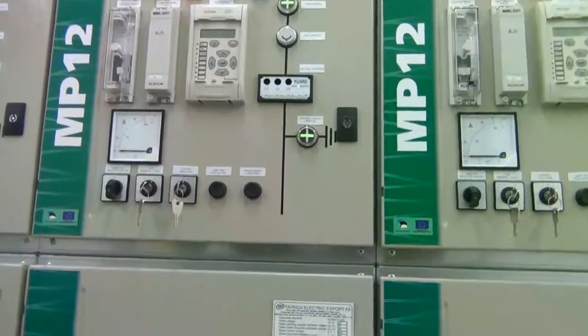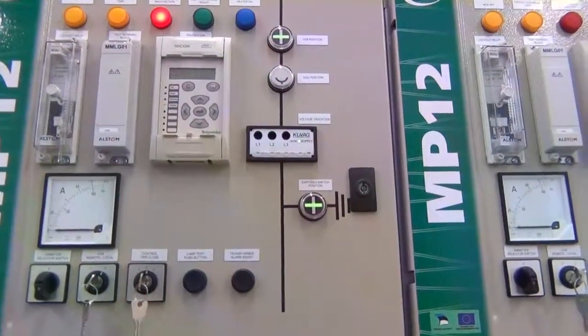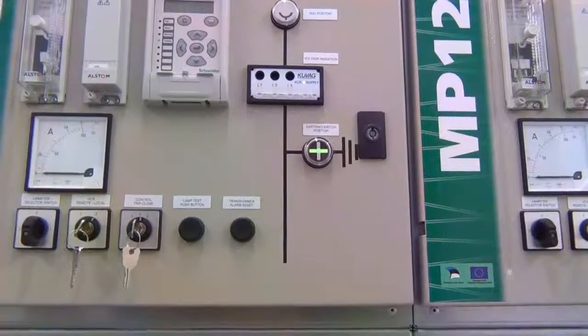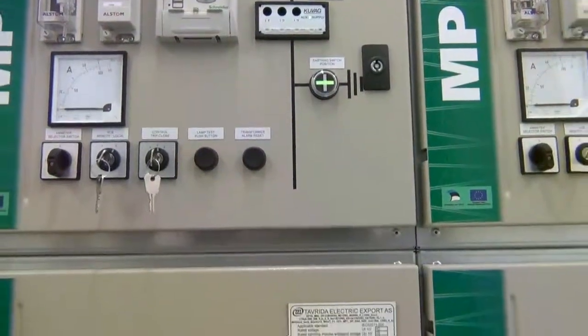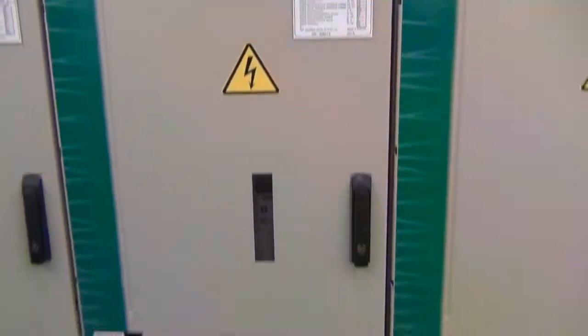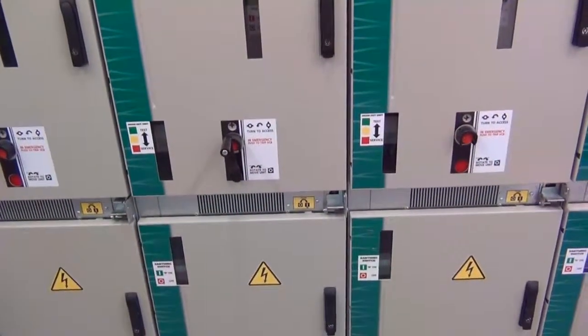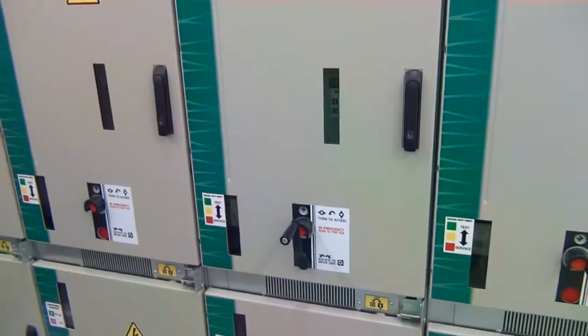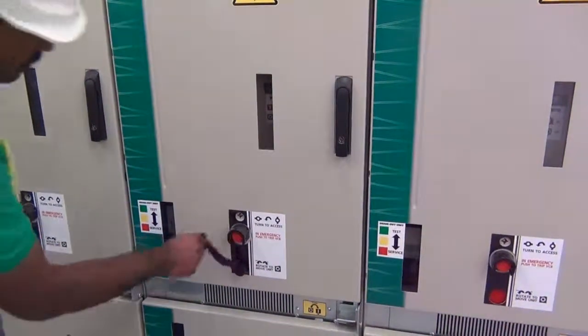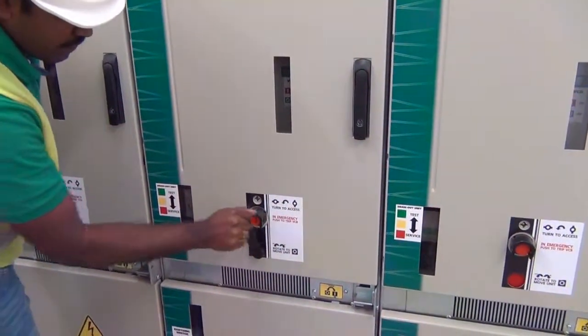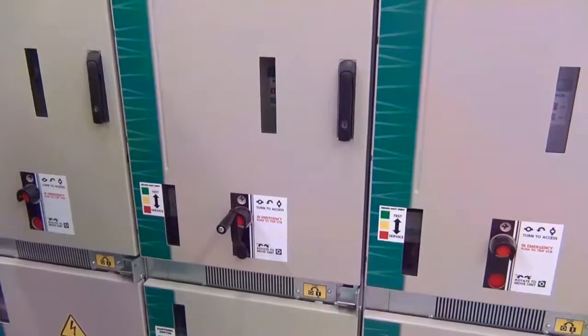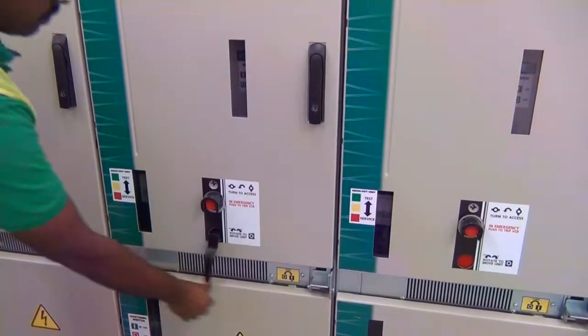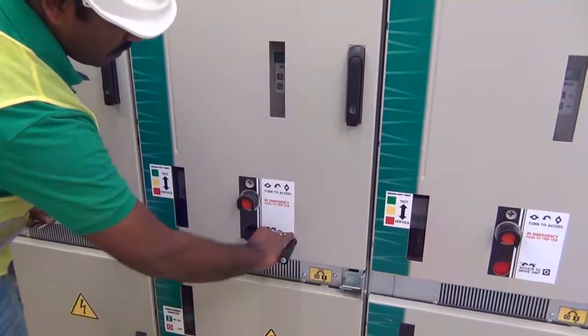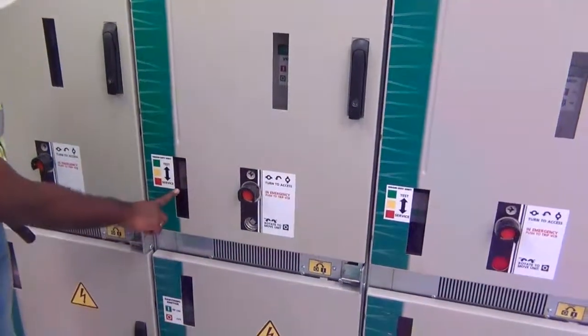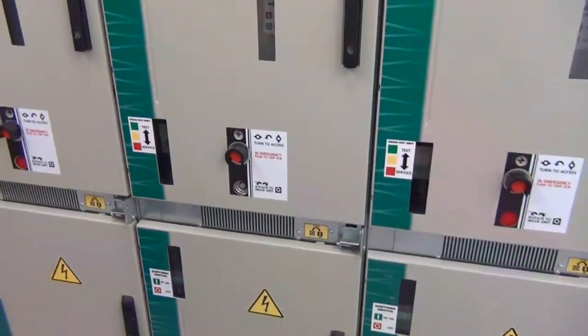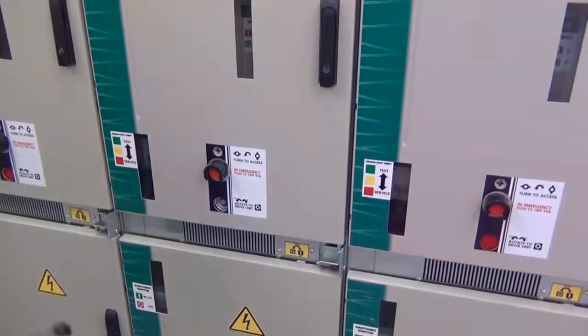We will check the interlocks. At this moment of time, the breaker is in test position, the earthing switch is on. In such a condition, you should not be able to rack in the breaker. So we will try and push in the breaker, and as you can see, it is not possible to do that. In order to do that, first we will have to open the earth switch.